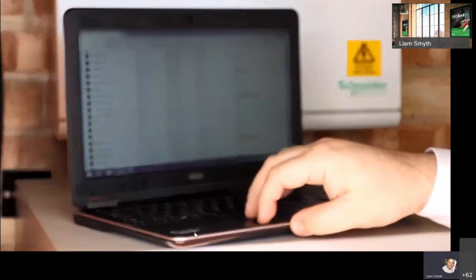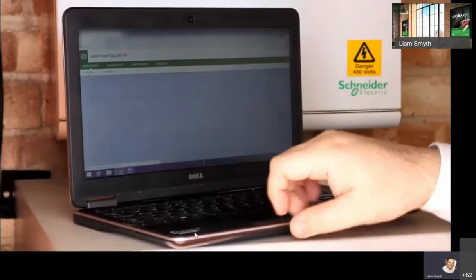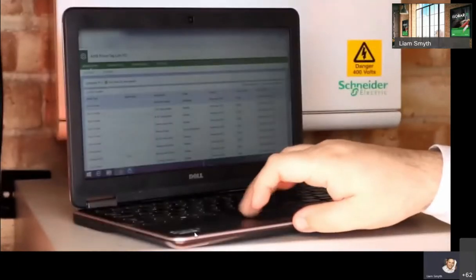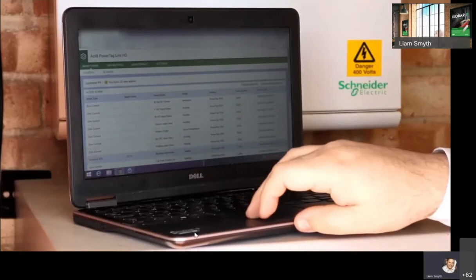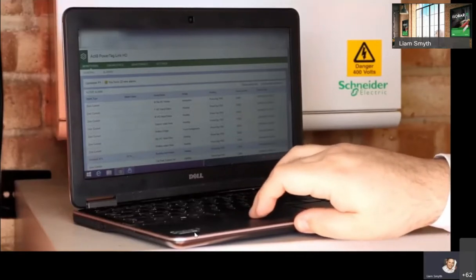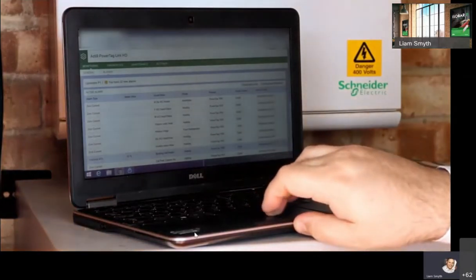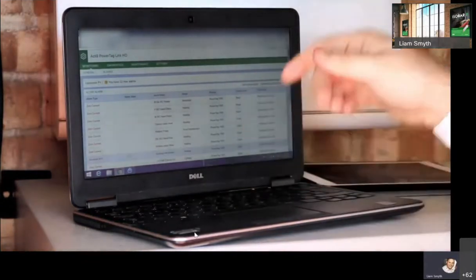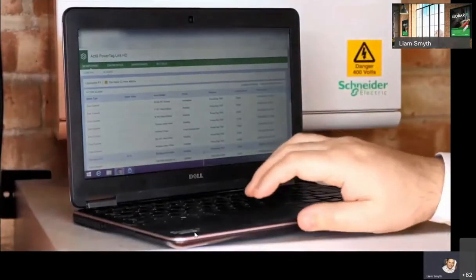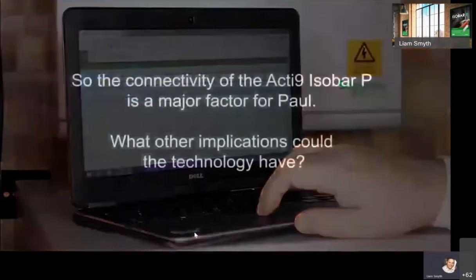So there's 40 circuits on this one concentrator device, which I've dialed into. If I look at the alarms, I go into the alarms page. The alarms page, all that does is tell me that there's 0 current. So there's nothing being used at the moment, but there was one where I had an overload of 45%. And what it told me was the booking hall heater went to 53%. Now, if I want to, I can actually email all the content of that alert and the times and the dates to myself. I can even set it up so it can email my help desk. However, for 45% overload, I don't need to. But it's interesting to just understand the dynamics of how circuits work.